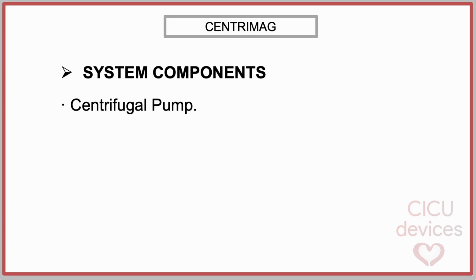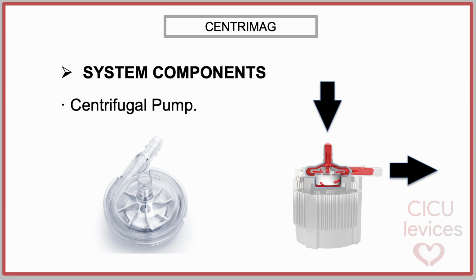The pump consists of a disposable pump head containing a rotor that is fully suspended by a magnetic field, eliminating the need for mechanical bearings or seals. This contact-free design minimizes friction, heat generation, and areas of blood stasis, thereby reducing the risk of hemolysis and thrombus formation. Blood enters the pump through the central inlet and is propelled radially outward by the rotating impeller, generating flow through centrifugal force. The blood is then directed toward the outlet, creating a continuous, non-pulsatile flow.